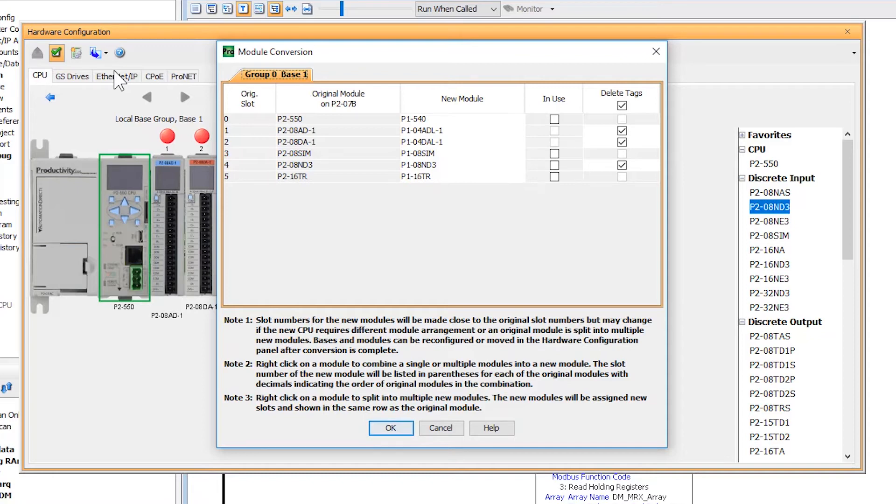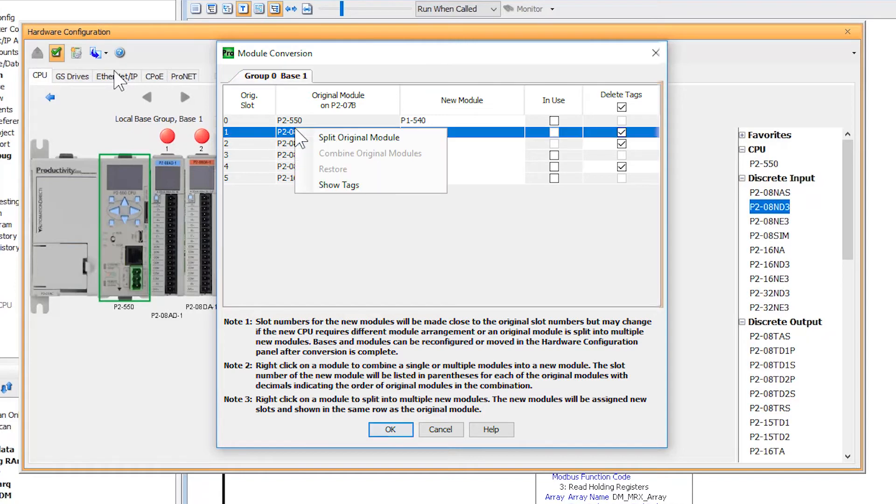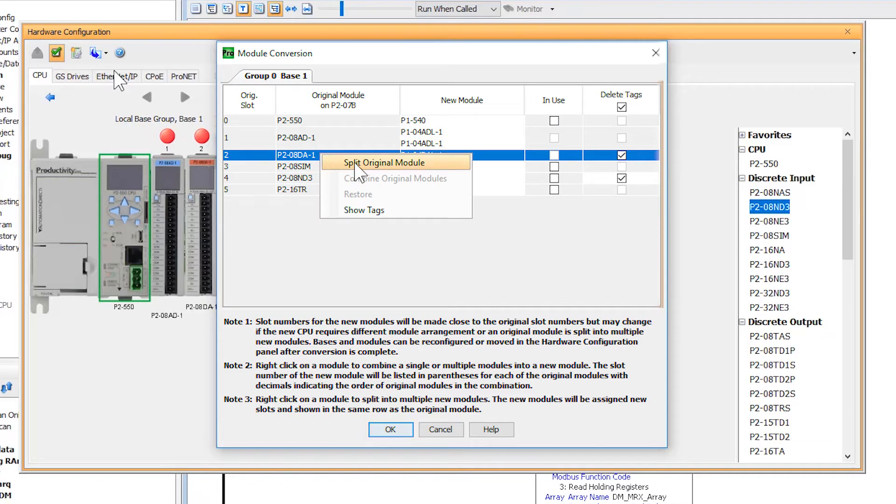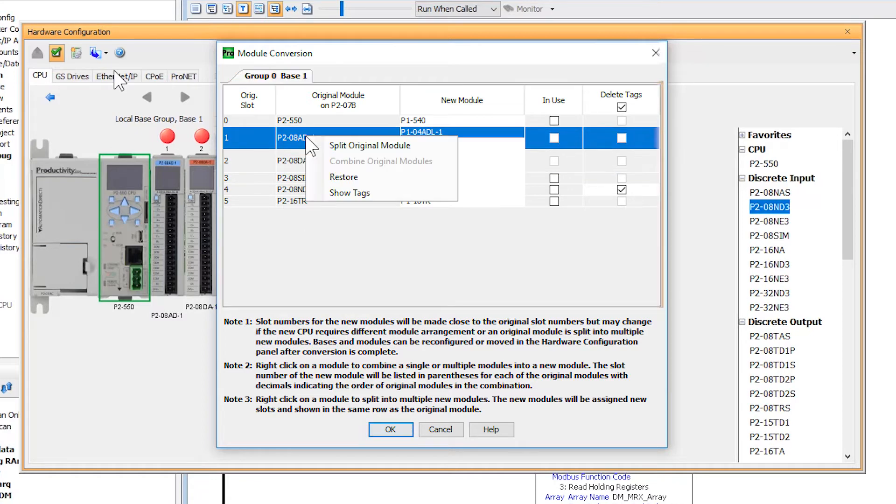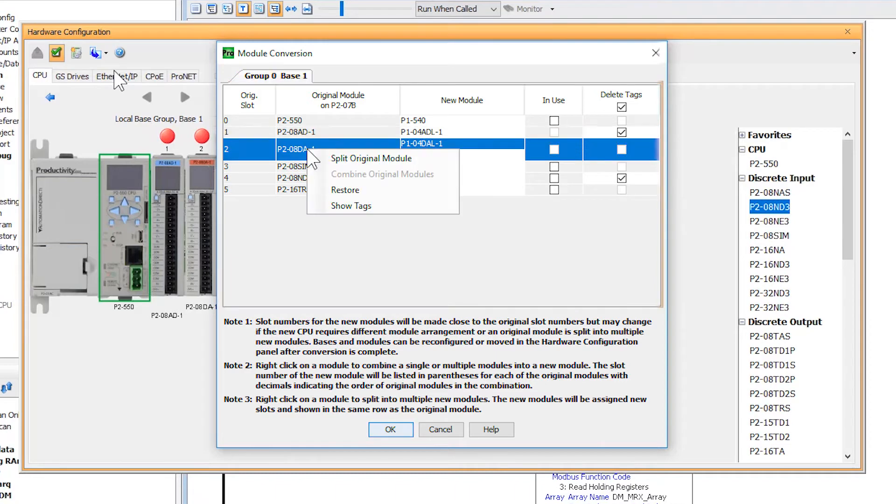The previous modules used in the P2000 system were of an 8-point type, and in the P1000, they are a 4-point type. If I needed to keep all this analog I/O, I can right-click on the original modules and then select split original module. As you can see, this takes the original 8-point modules and splits them across two 4-point modules each. But as I am not using all 8 points, I will go back to the 4-point modules by selecting restore.